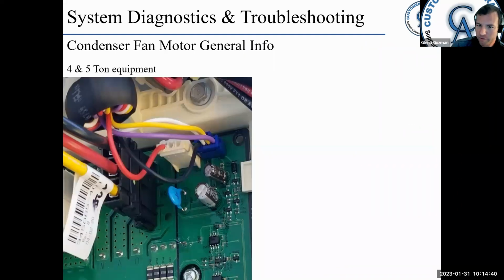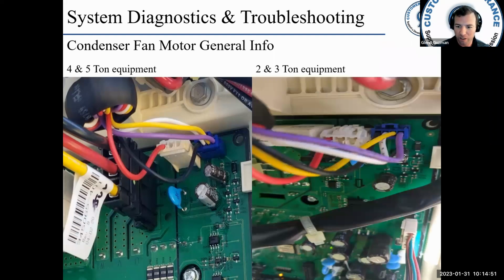Condenser fan motor. I got some general info for you here. This is the 4 and 5 ton equipment. And the picture on the right is a 2 and 3 ton equipment. It's basically the same. The plugs look a little bit different. You can see it's just the physical nature of the plug, but the wire colors are all the same. Now, the fan connections are the same, right?